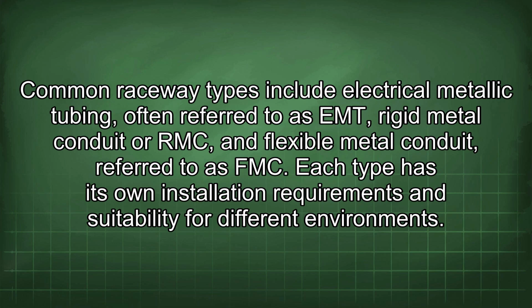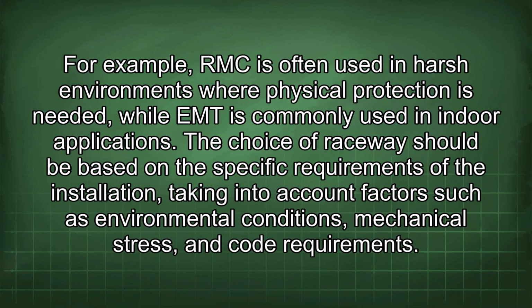Each type has its own installation requirements and suitability for different environments. For example, RMC is often used in harsh environments where physical protection is needed, while EMT is commonly used in indoor applications. The choice of raceway should be based on the specific requirements of the installation, taking into account factors such as environmental conditions, mechanical stress, and code requirements.